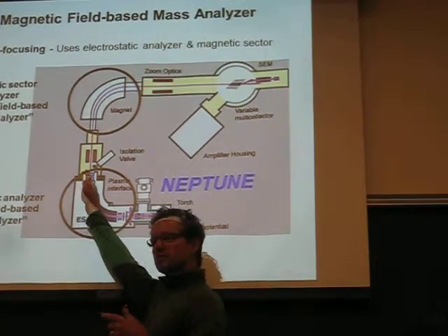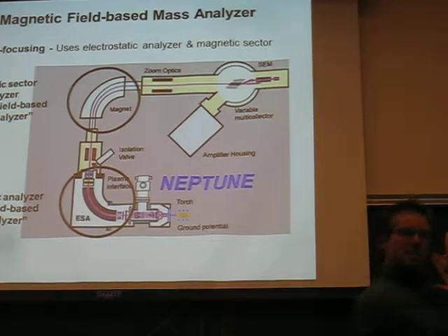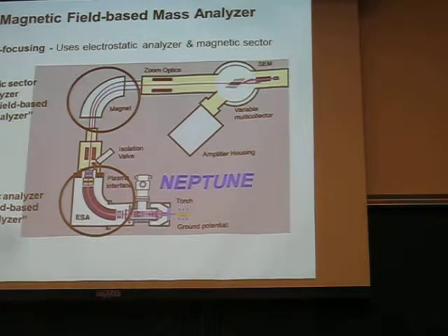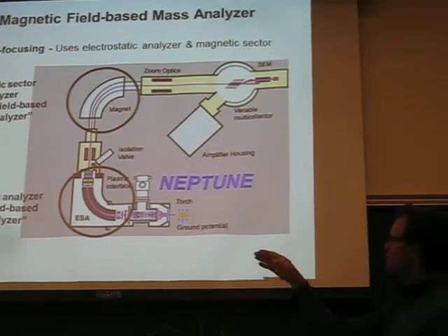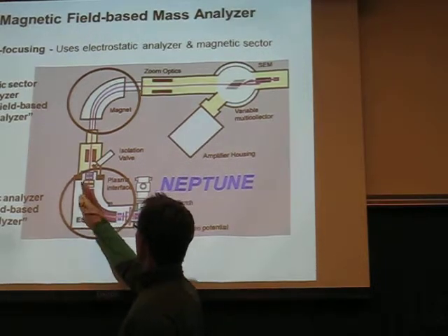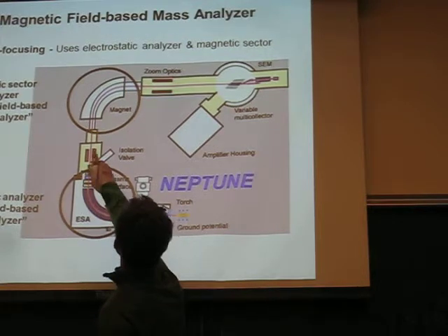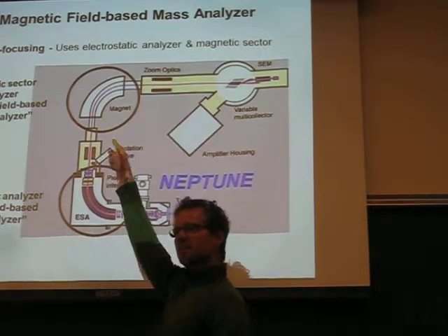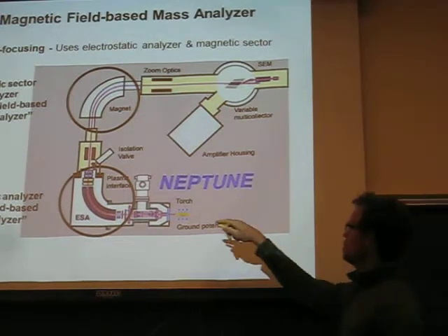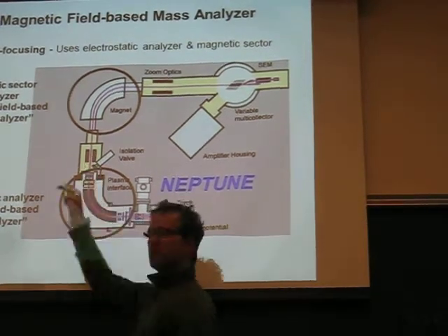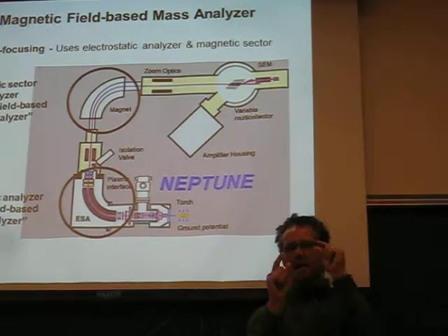And that radius in the trajectory is there because it's much more difficult to channel an ion across a curved trajectory than it is in a straight line, right? And so they can steer the ions you want through this electrostatic analyzer, through some additional focusing lenses, and ultimately into a very strong magnetic field. These magnets are probably about this big around, and the flight tube, which is what they call the thing the ions travel through, measures about like this. So it's a really skinny and narrow space.